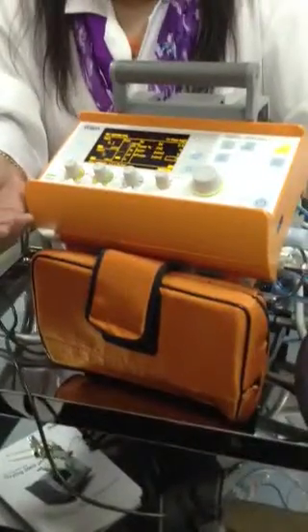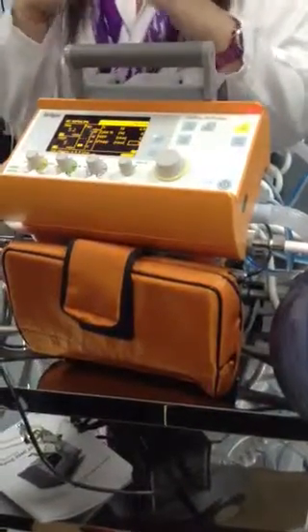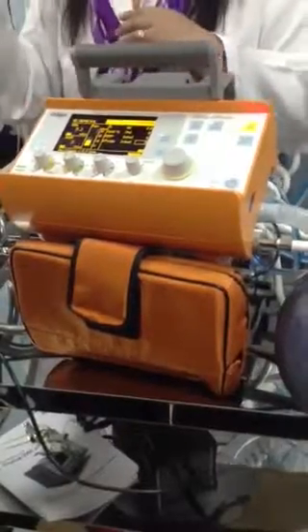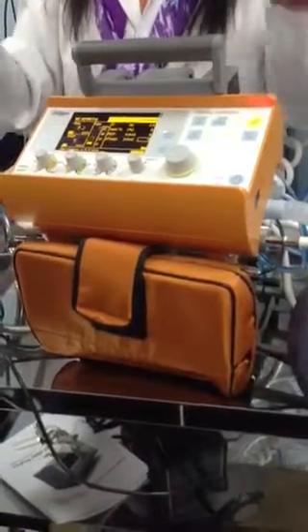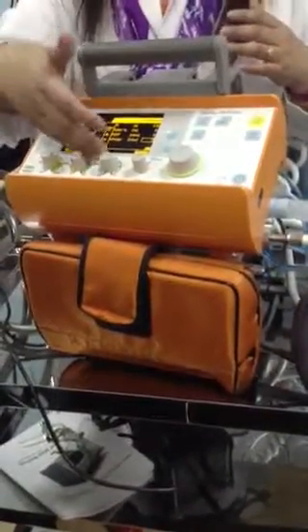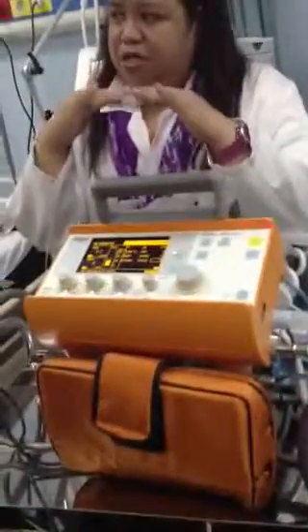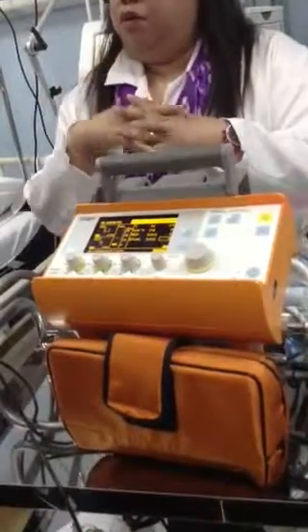Volume control, controlled mechanical ventilation. It becomes controlled when your patient is not giving spontaneous breathing. If assisted, your machine will give and your patient is also breathing. For your synchronized intermittent mandatory, both your machine and your patient is breathing, but it synchronizes to prevent the fighting with the ventilator. So, pag nag-breathe yung patient mo, your machine is breathing or not breathing. If your patient will breathe and your machine will both breathe because you preset the respiratory rate, the machine will adjust with your patient. It synchronizes with the patient to prevent fighting with the machine or yung alarm.